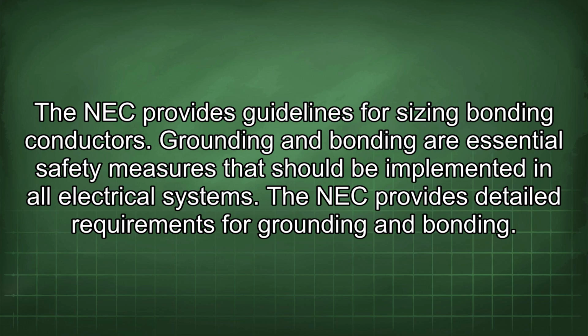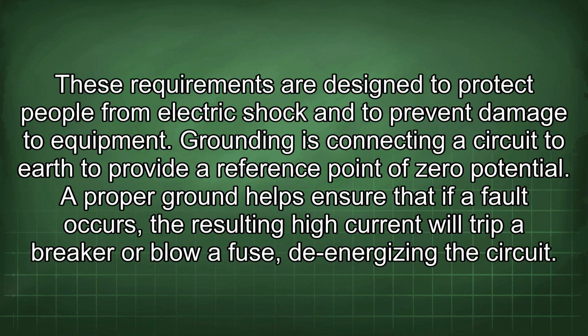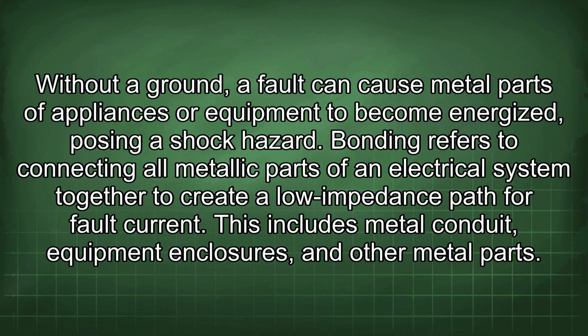Grounding and bonding are essential safety measures that should be implemented in all electrical systems. The NEC provides detailed requirements for grounding and bonding. These requirements are designed to protect people from electric shock and to prevent damage to equipment. Grounding is connecting a circuit to earth to provide a reference point of zero potential. A proper ground helps ensure that if a fault occurs, the resulting high current will trip a breaker or blow a fuse, de-energizing the circuit. Without a ground, a fault can cause metal parts of appliances or equipment to become energized, posing a shock hazard.